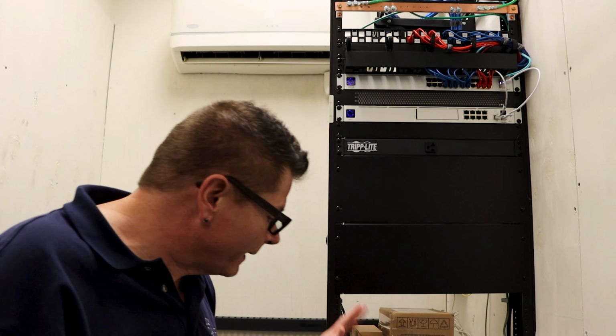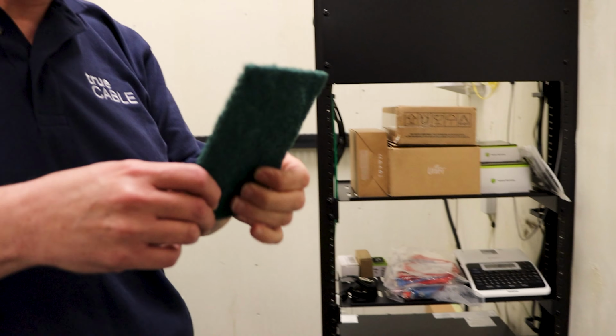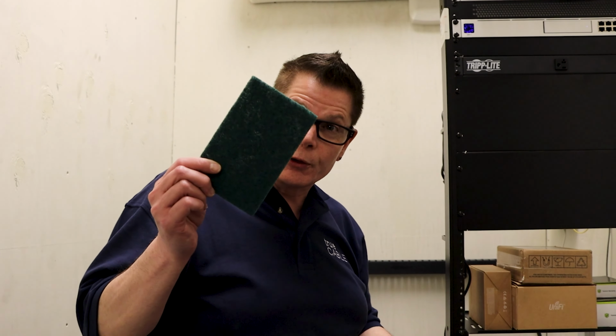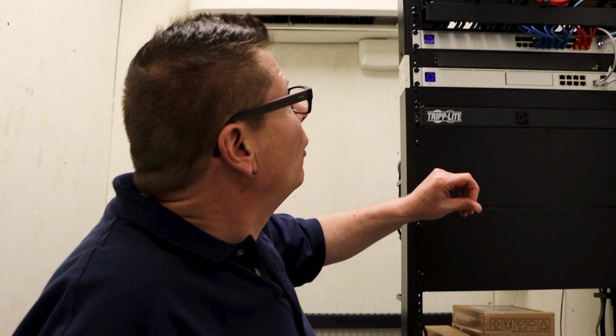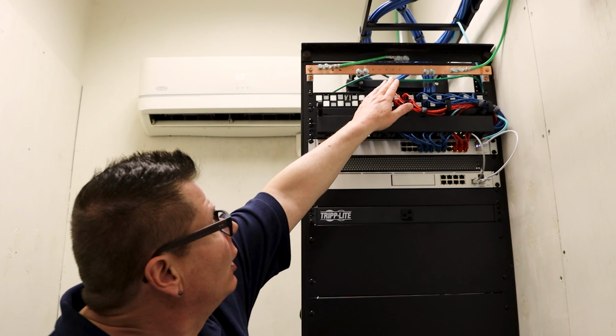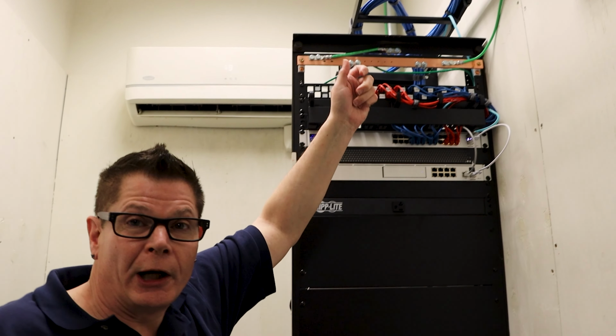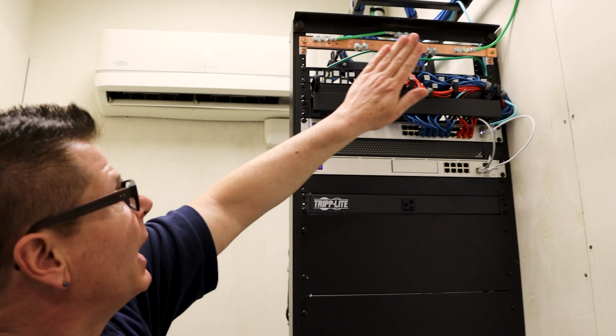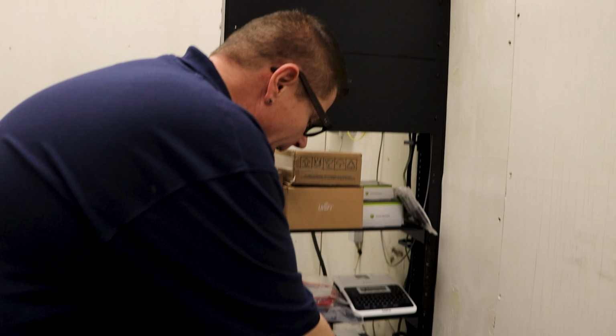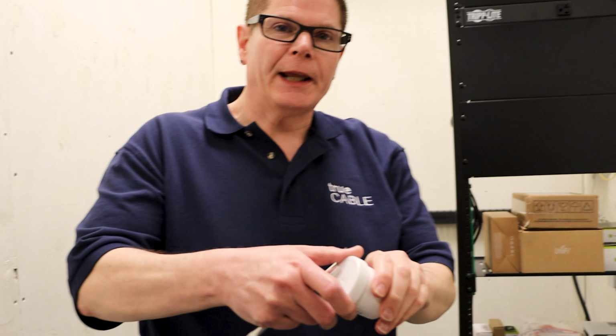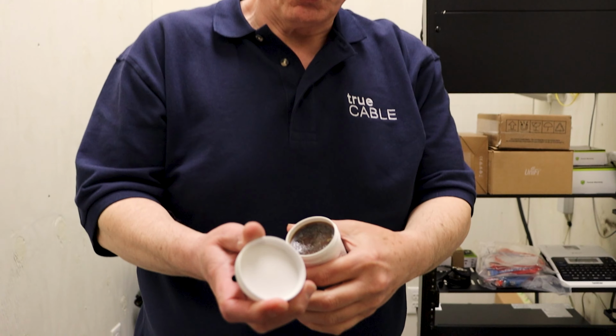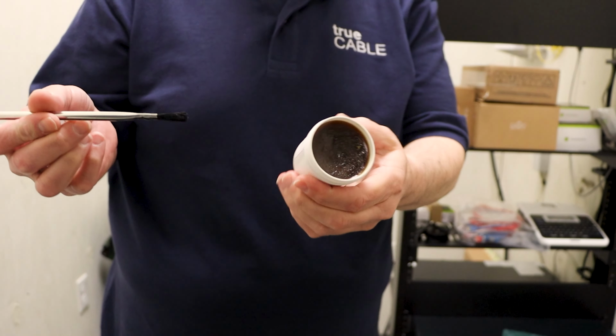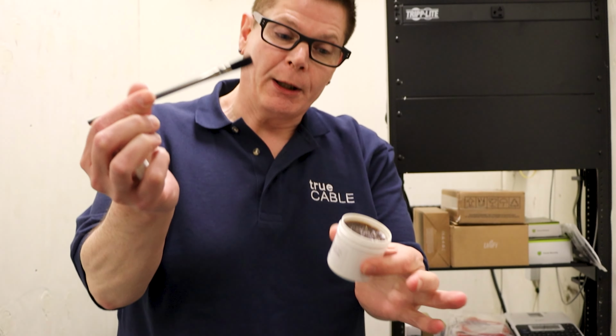So the best way of doing that, well, you can go the slow way, which is a Scotch-Brite pad, one of these green ones. The quick way is a drill with a wire wheel attachment. So what I did is when I attached that lug up here to the rack, I used a wire wheel attachment, made it bare metal, and then I prepped up that area that's bare metal with what's known as a no oxidation grease or paste, and you apply it with a brush.